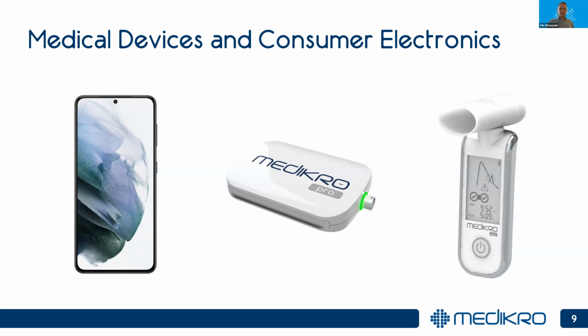Yes, it's visible. Yeah. So let's take our handheld device as an example on the right. So it has been tested for the safety standards. For example, the dropping. If you drop it, the regulation requirement is not as strict as our internal company requirements. So that device actually lasts 180 times from half a meter plus 120 times from 1 meter to the concrete, and it will still work. So there's no sharp parts, dangerous parts breaking out, and it still has the capability of doing the test. So it can have the scratches, but it will work.